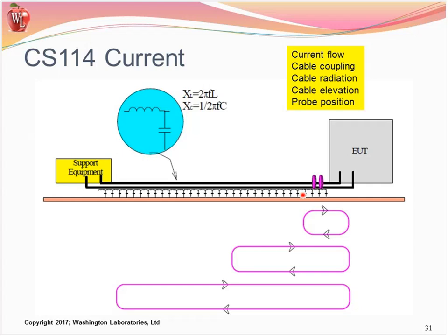What if I put these cables on a non-conductive surface, not a ground plane at all, but like on a common tabletop, 80 or 90 centimeters? The dielectric now has an air gap of 80 to 90 centimeters, and so the coupling mechanism requires current to go way around to get a return path. And as I do that, my series inductance increases significantly and lowers the overall current being produced. I achieve the drive level without attaining the test current.